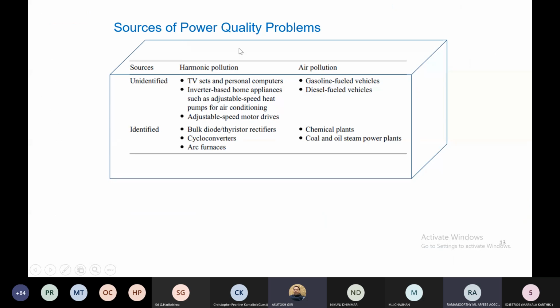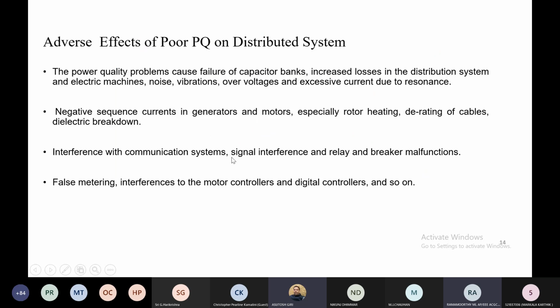These are the sources of power quality problems, unidentified and identified sources, two categories, equated from harmonic pollution to air pollution. TV sets, personal computers, inverter based home appliances such as adjustable speed heat pumps, adjustable speed motor drives, are creating harmonic pollution in the system. Also bulk diodes, thyristors, cycloconverters, and arc furnaces are creating harmonic pollution in the system.